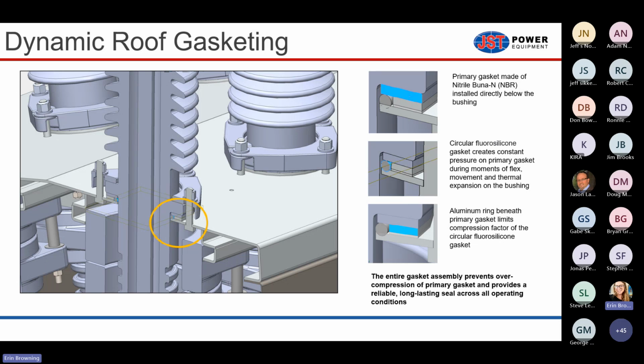And getting through that roof, I mean, that's a very vulnerable compartment, right? Because that's where the embedded poles are located. You have exposed buswork in that compartment. You really don't want anything in there that's not supposed to be in there. So as much as we can do to keep sand and water out of the high voltage compartment, we will. So we call this a dynamic roof gasketing system because, again, this circular gasket is responsible for creating an upward force on the top gasket at all times.